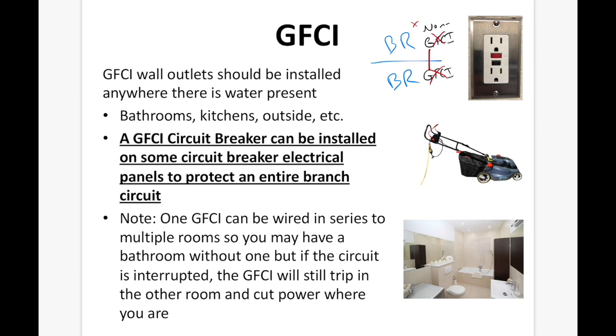So if you have a multi-story house, let's say you have a bathroom upstairs and a bathroom downstairs, with a GFCI down here and a non-GFCI up here. If you trip the circuit upstairs, this non-GFCI is still wired to the bottom GFCI. Since this reading is done so precisely and quickly, even if you trip it upstairs, it's still going to cut the power to this GFCI and thus the non-GFCI almost immediately.